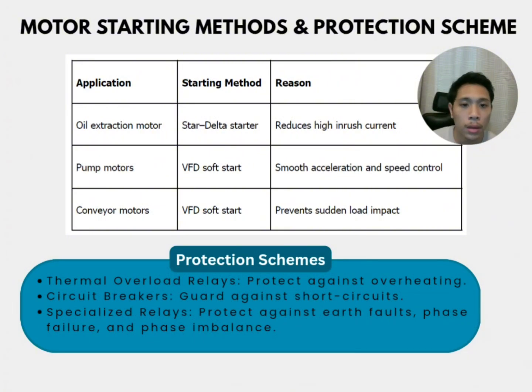Continue to the next slide, which is motor starting methods and protection scheme. One of the biggest challenges in this system is managing the inrush current when the motor starts. To handle this, we use two different strategies. For our largest motor, which is the 30 kilowatt, we use a star delta starter. This effectively drops the starting current to just one third of its normal level, which prevents a power surge that could trip our microgrid. For the pumps and conveyors, we have integrated variable frequency drives.